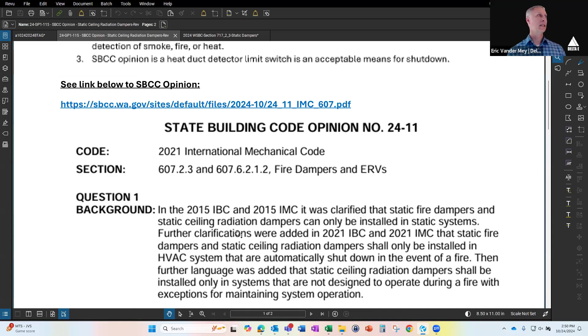The council did say that even in a small, like 100 CFM system, you would have to shut down that ERV. The council acknowledged that the code is silent on acceptable means of shutdown for small systems. They also rendered the opinion, and we can look at these in more detail, that a duct heat detector or a heat duct detector limit switch would be an acceptable means of shutdown.